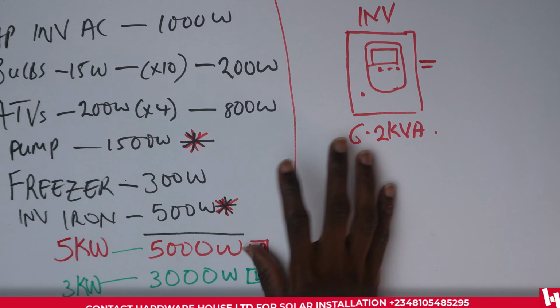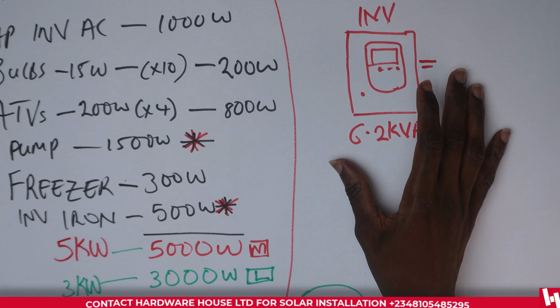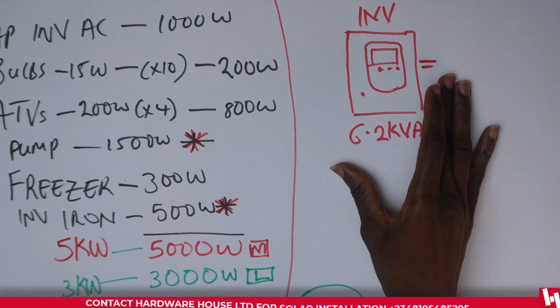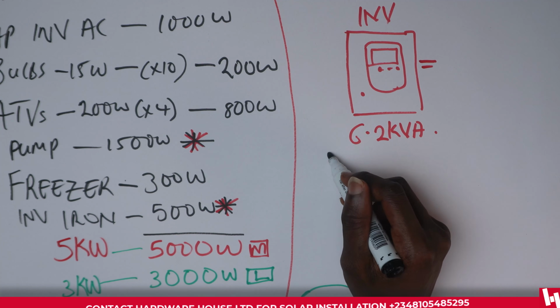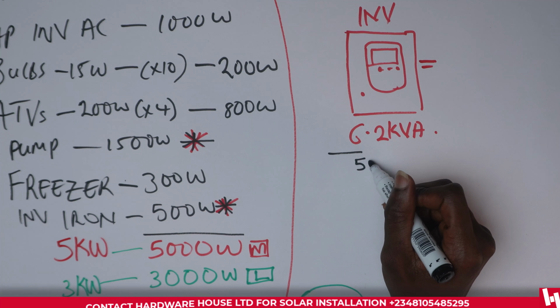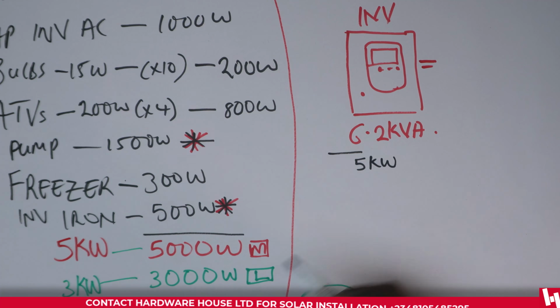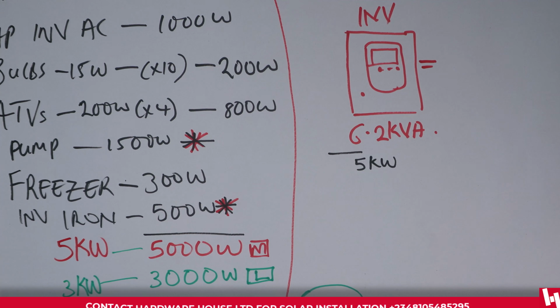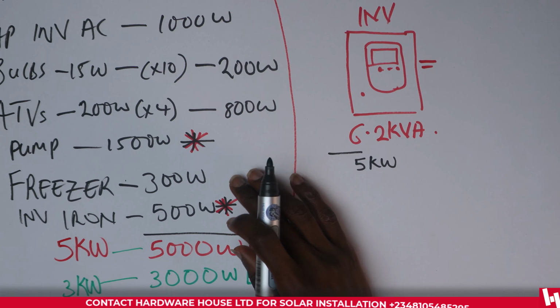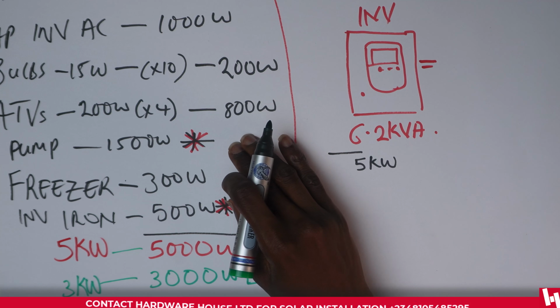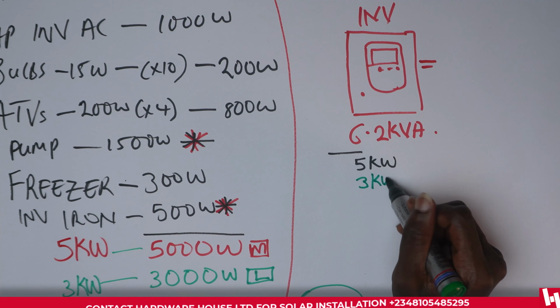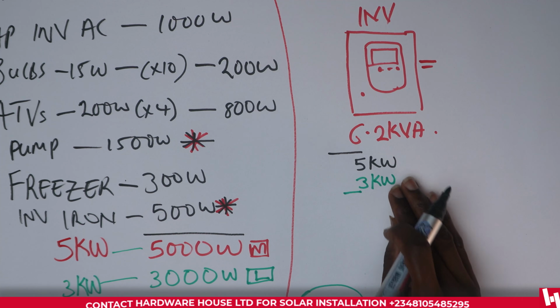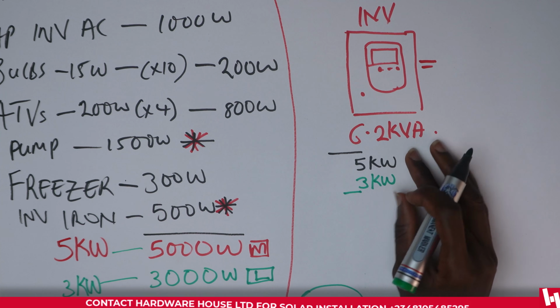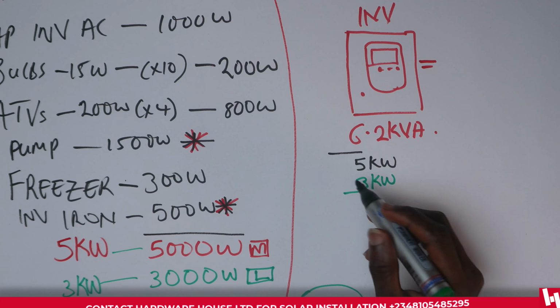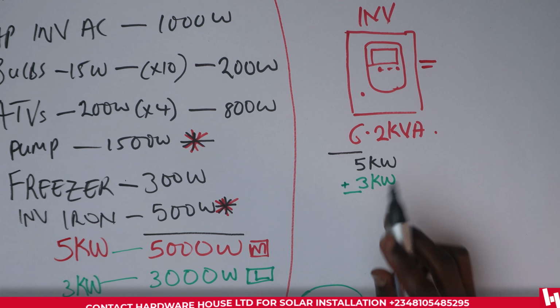the solar panel. So in order to calculate the kind of battery that is going to be perfect for this system, remember our client does not want an overkill. So for the daytime load, this inverter is doing 5 kilowatts. For the nighttime load, however, the freezer is going to stay on. The pressing iron off, pumping machine out of the picture. So 3 kilowatts is what we'll be using as our nighttime load. So we're going to be calculating for the battery based on the nighttime load, while the 5 kilowatts will be the daytime load because it's being aided by the solar panels.